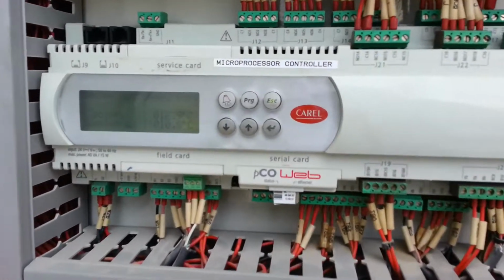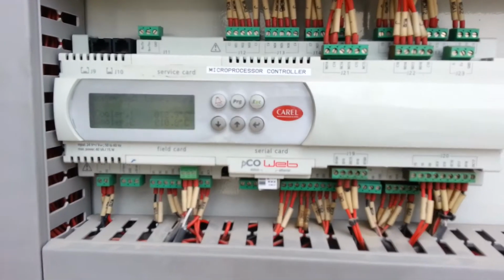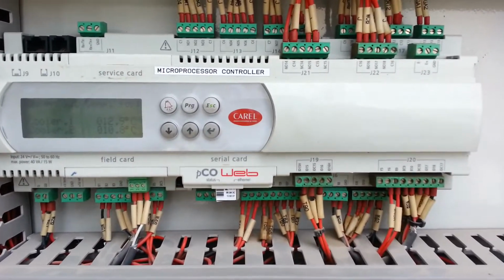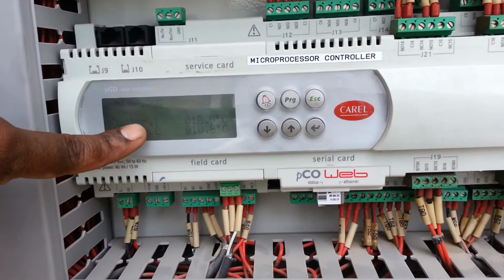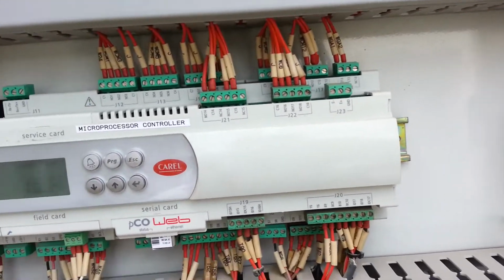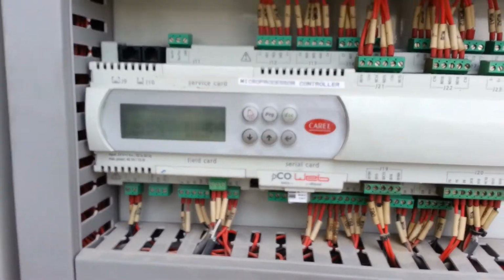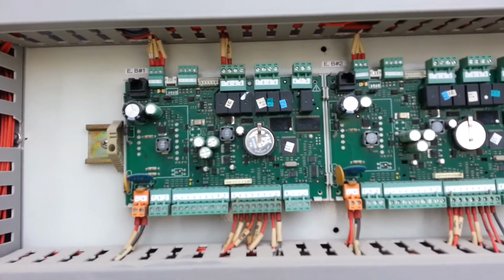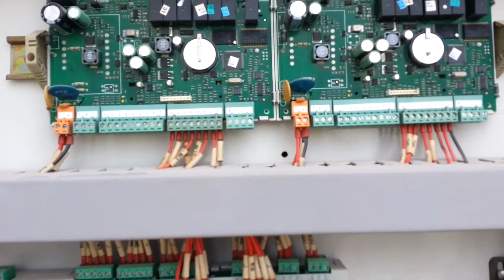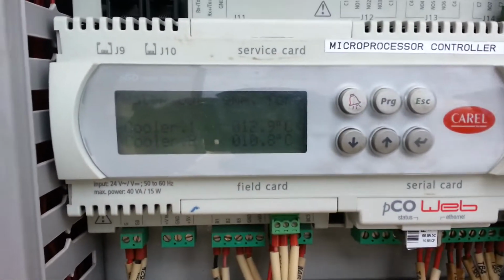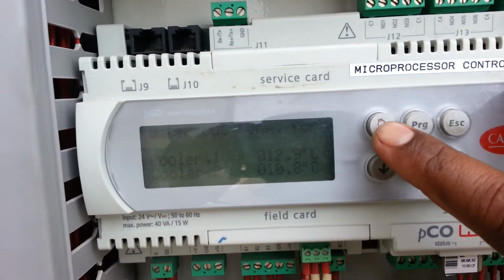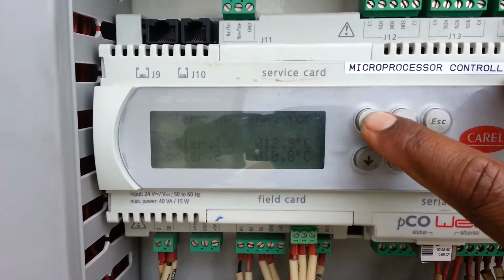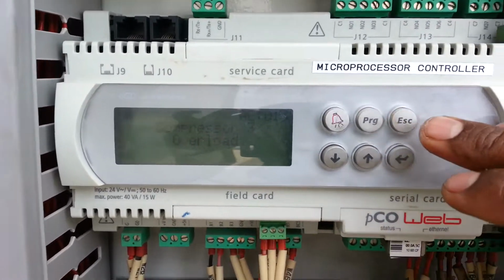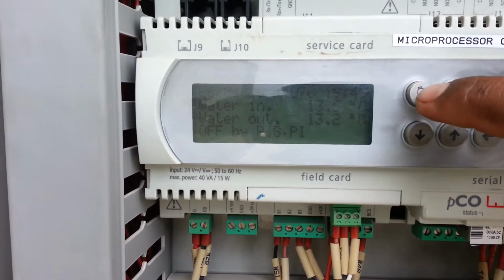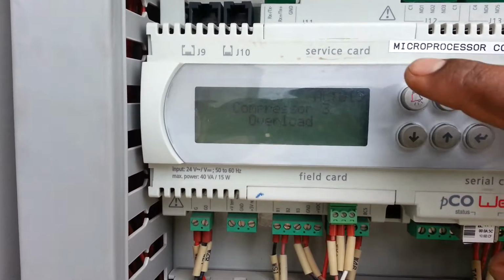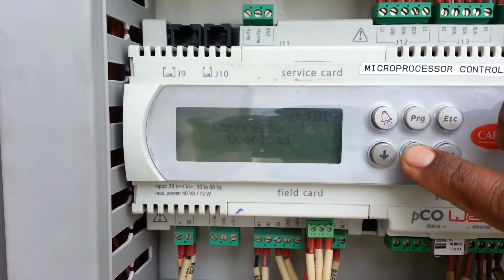And here is the main controller, Carel. This is the main controller. In manual mode, this controller is controlling all the chillers. And here there are 2 extensions supporting the main controller. Here we can see there is an alarm symbol. If we press the alarm, then we can see any fault, and it will show through this alarm.